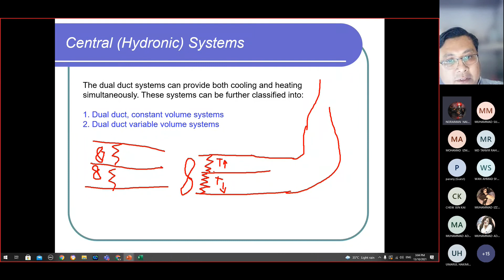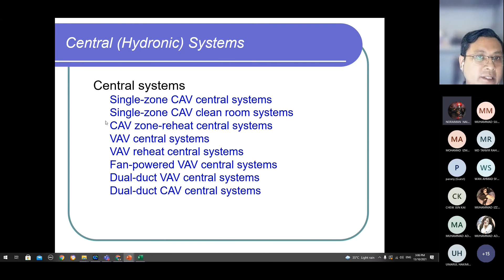Okay, central system single zone CAV, single zone CAV clean room system, central system CAV reheat, VAV central system, VAV reheat central system, fan power VAV central system. So this one is a type of the dual duct system. In this distribution, you can see the mixing. Okay, if you recognize, every duct will represent one condition, and another duct another condition. This is why we can control each zone with a different condition.